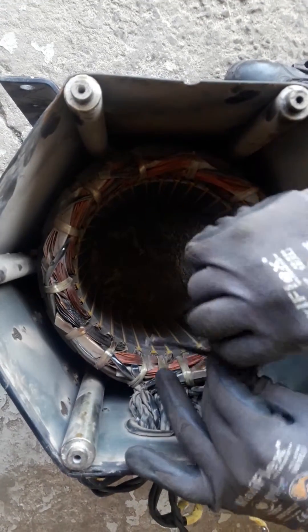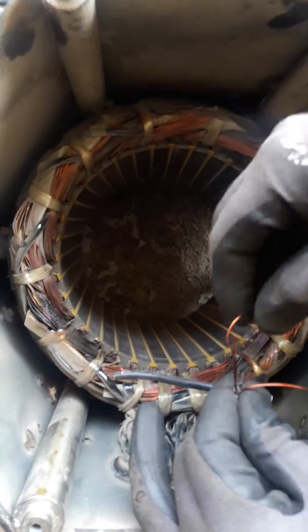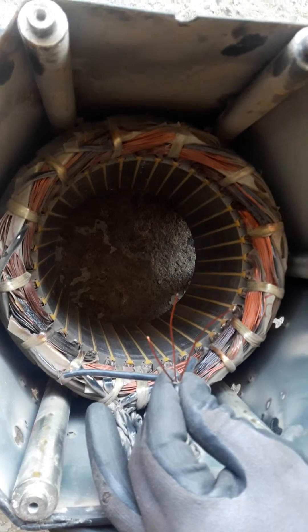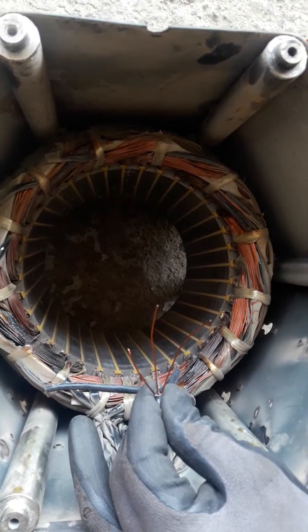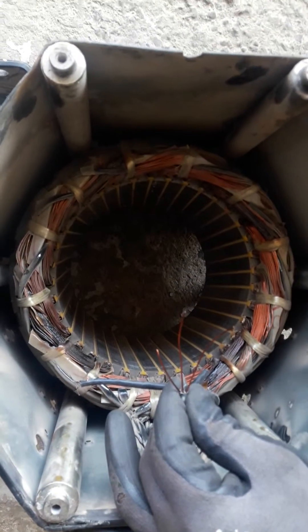The sleeve is now removed. Under one sleeve you can see how many copper wires there are — as you can see, there are three copper wires. So three wires are used to rewind; each turn combines three wires to wind the new coils. This data you need to write down.